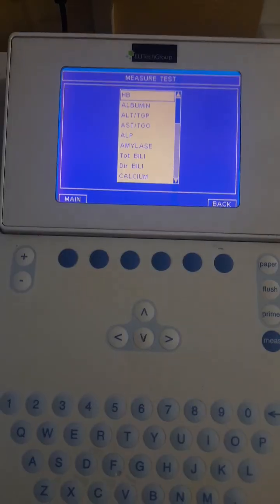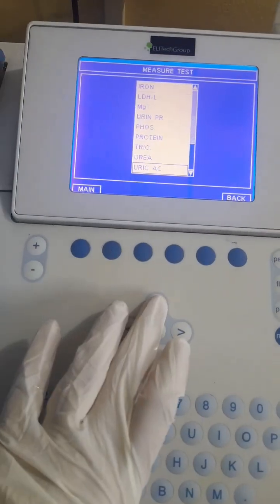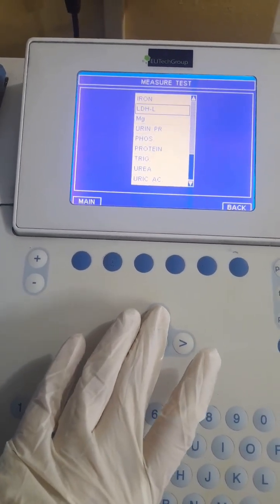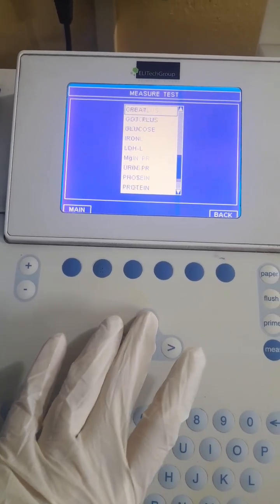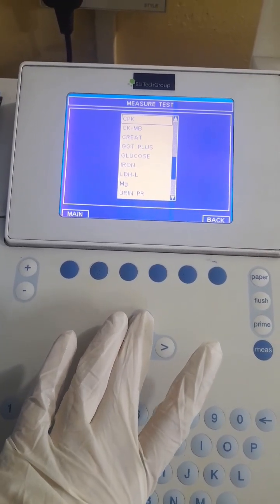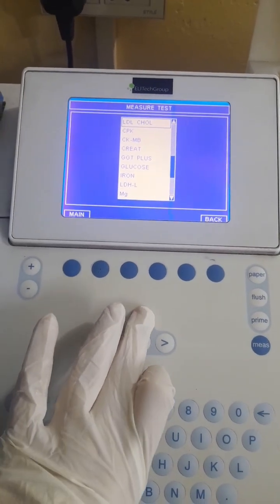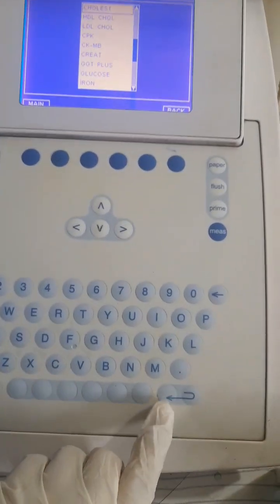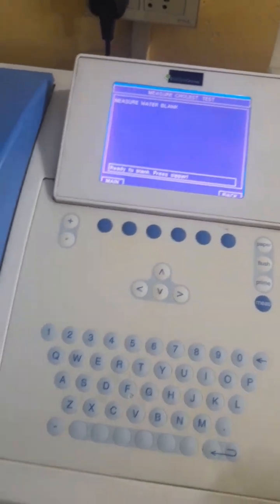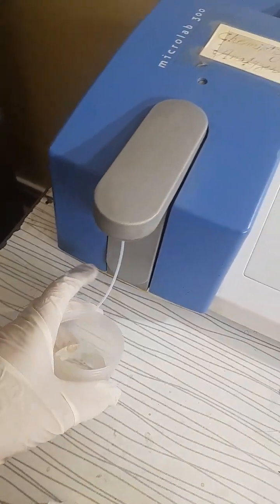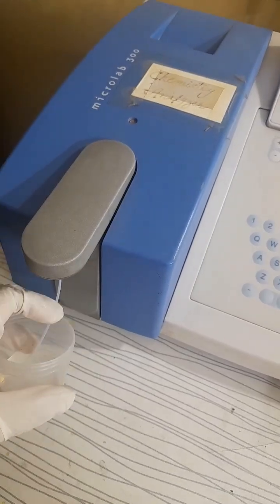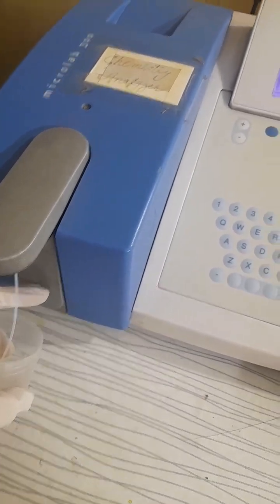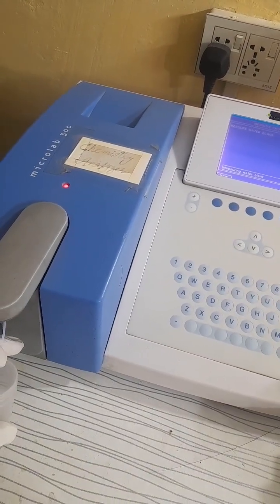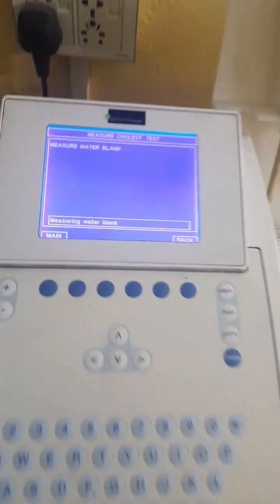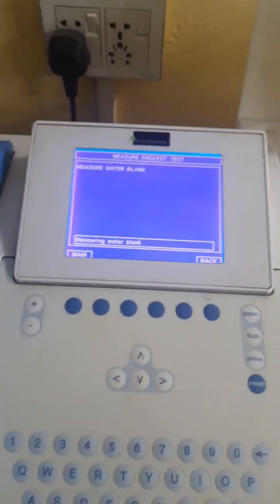Now I have come to the machine. I put it in the measuring position, and then I choose which parameter I have to measure, which is cholesterol. I move the upward arrow and choose cholesterol, press the enter button, and move toward the cholesterol. Basically, this machine requires a water blank. You just have to put in distilled water and push the button. There will be a red light, and then a sound saying it requires enough water. Then it measures the water blank.